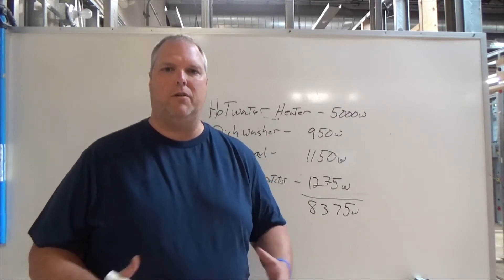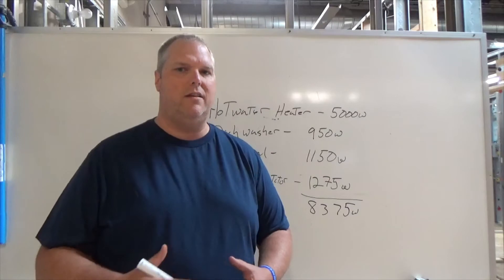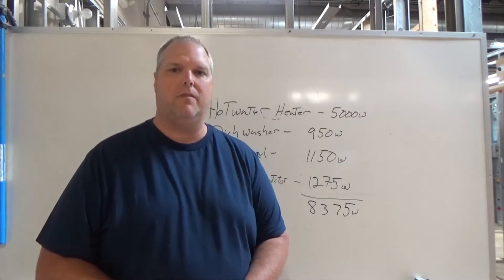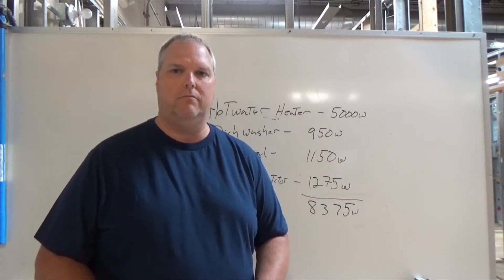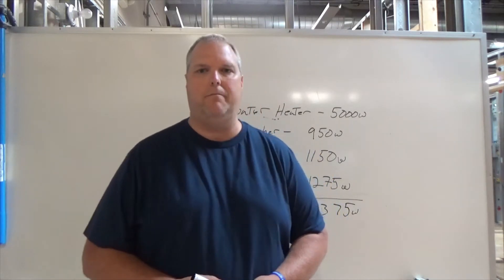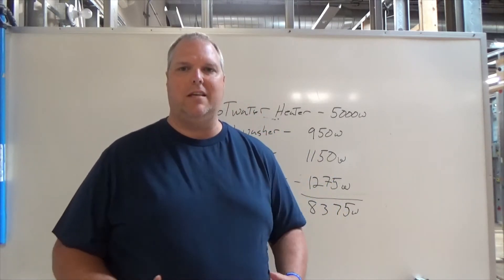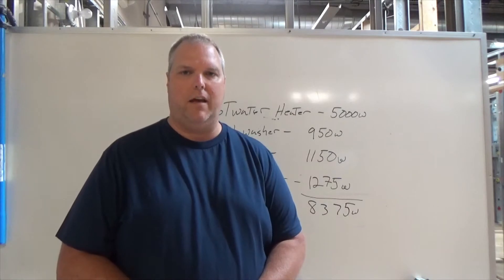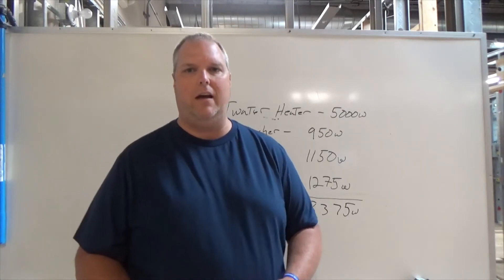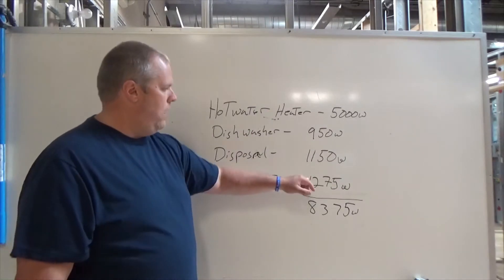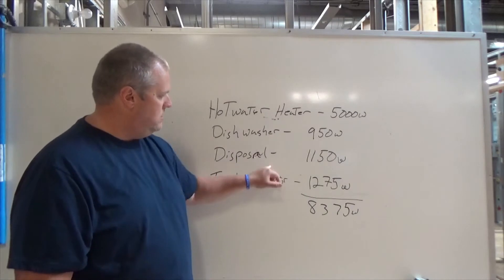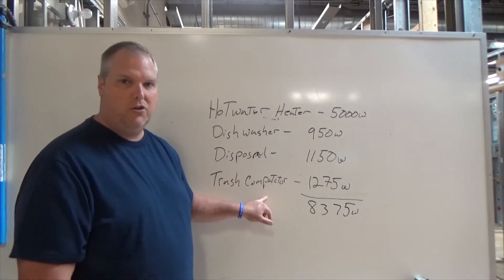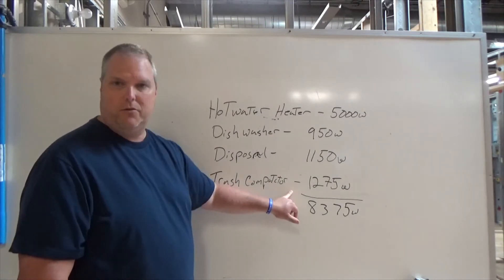Here's what we have to remember, especially as an electrician or new apprentice: when we size a motor, we size the largest motor at 125 percent. Every motor after that we size at 100 percent. With that in mind, when sizing these out — the trash compactor and the disposal are the two possible largest motors — the trash compactor becomes the largest motor.